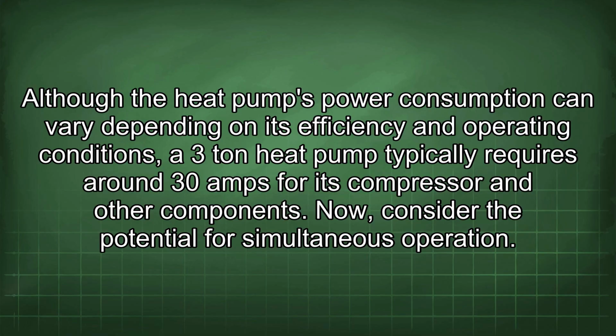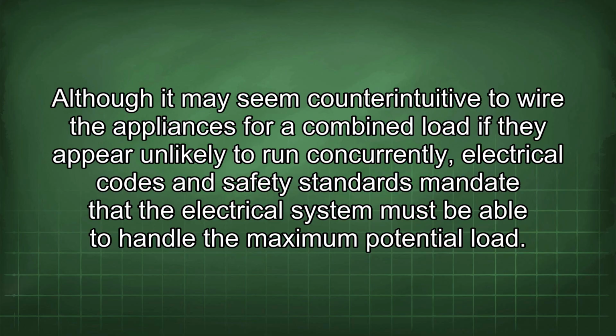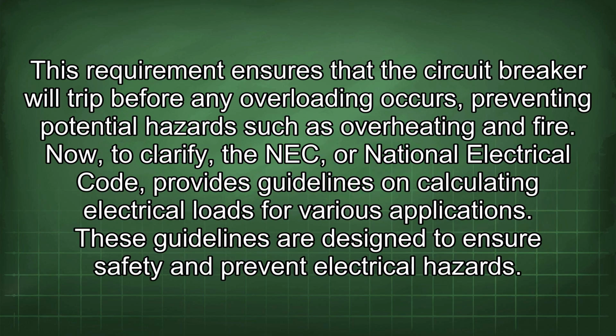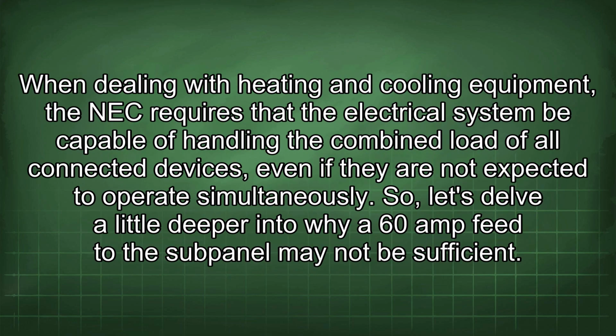Now consider the potential for simultaneous operation. Although it may seem counterintuitive to wire the appliances for a combined load if they appear unlikely to run concurrently, electrical codes and safety standards mandate that the electrical system must be able to handle the maximum potential load. This requirement ensures that the circuit breaker will trip before any overloading occurs, preventing potential hazards such as overheating and fire. Now, to clarify, the NEC, or National Electrical Code, provides guidelines on calculating electrical loads for various applications. These guidelines are designed to ensure safety and prevent electrical hazards. When dealing with heating and cooling equipment, the NEC requires that the electrical system be capable of handling the combined load of all connected devices, even if they are not expected to operate simultaneously.